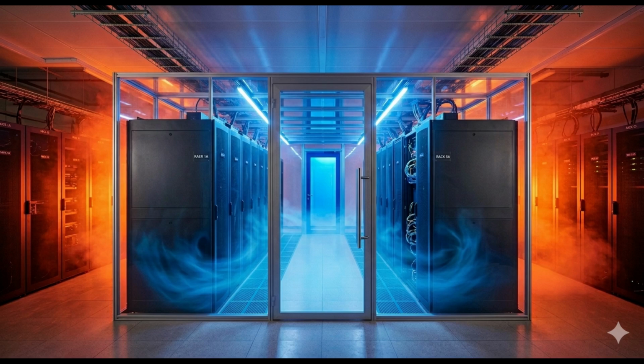Yeah. And theoretically, that gives you about a 99.67% availability. Which sounds great to a layperson, 99.67%. It sounds great until you do the math. In a 24/7 operation, that equates to roughly 28.8 hours of downtime every single year. Yeah, almost 29 hours offline. For a major financial institution or a cloud provider, that's catastrophic.